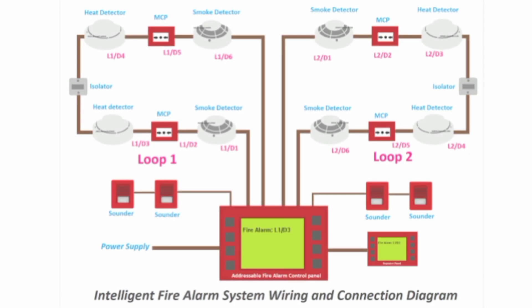In our next type of system, which is an intelligent fire alarm system, each detector effectively incorporates its own computer which evaluates the environment around it and communicates to the control panel whether there is a fire, fault, or the detector head needs cleaning.